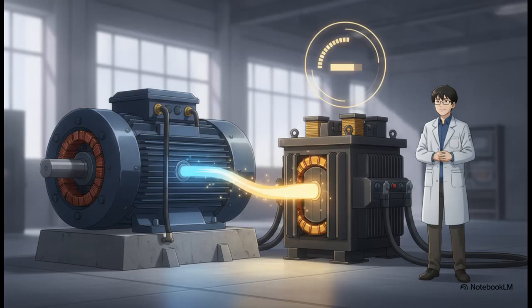If you end up working at a large Kerala Water Authority pump station, you're for sure going to see these everywhere. Now, for the really massive industrial machines, we step up to the auto transformer starter. This relies on applying a reduced voltage initially to get a nice, smooth start, and then it kicks over to full voltage once things are moving. For high-powered motors and heavy-duty machinery, this kind of voltage reduction tech is essential.